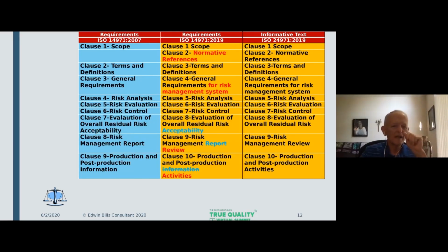The general requirements, clause 4, became general requirements for risk management system. Notice the word system here. We're now establishing requirements for a risk management system. And then 5, 6, and 7 stayed the same. In clause 8, they struck the word acceptability out of evaluation for overall residual risk. And in clause 9, the risk management report was struck and replaced with review, and we'll talk about that a bit later. And then finally, clause 10, which was the old clause 9, we took out the word information and changed it to activities. So there are activities that are required in the production and post-production activity area.